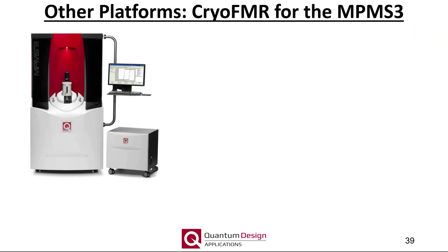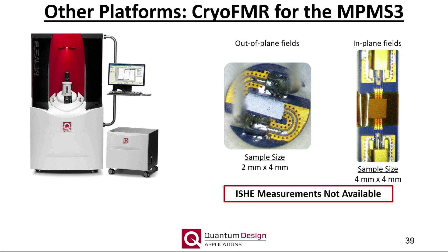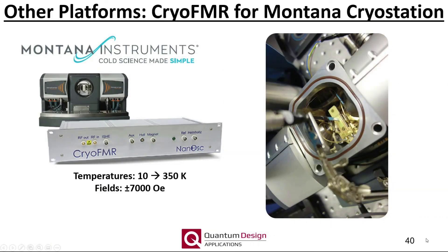Moving on to other platforms compatible with the spectrometers offered by NanOsc. Cryo-FMR measurements can be performed within the much smaller diameter sample chamber of the MPMS-3 by special coplanar waveguides. Both in-plane and out-of-plane measurements are possible. Note, for out-of-plane measurements the maximum sample size is about 2 mm by 4 mm. A further restriction is in regards to inverse spin Hall effect measurements, which are not possible with the cryo-FMR probe available for the MPMS-3. Measurements can be performed over the same temperature range as that for the PPMS product line and up to 7 Tesla. Continuing on with cryo-FMR, the Montana Cryo Station can also perform FMR measurements for in- and out-of-plane fields. The temperature range is 10 to 350 Kelvin at fields up to 7,000 Oersted. Also note the cryo-FMR instrument can also be integrated into other magneto cryostats on the market. If you're interested, please contact your local Quantum Design office for more information.